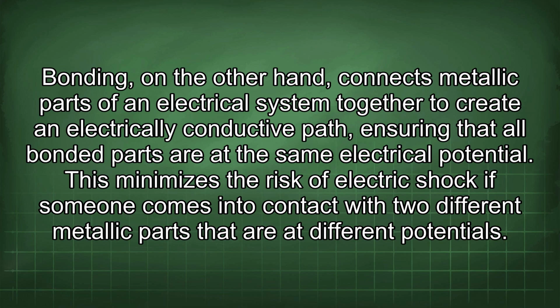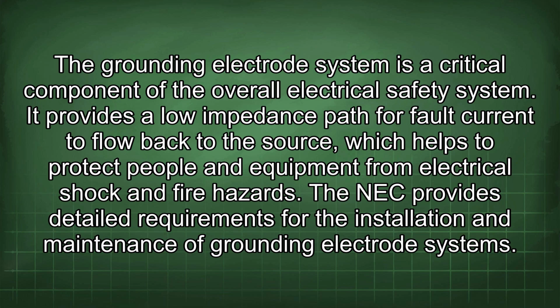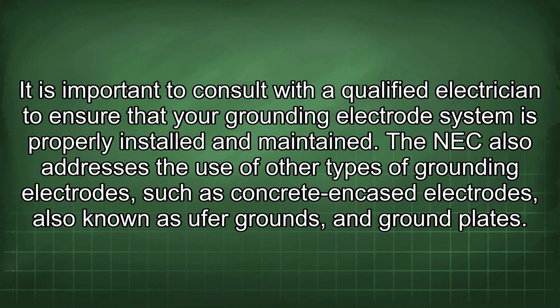This minimizes the risk of electric shock if someone comes into contact with two different metallic parts that are at different potentials. The grounding electrode system is a critical component of the overall electrical safety system. It provides a low impedance path for fault current to flow back to the source, which helps to protect people and equipment from electrical shock and fire hazards. The NEC provides detailed requirements for the installation and maintenance of grounding electrode systems. It is important to consult with a qualified electrician to ensure that your grounding electrode system is properly installed and maintained.